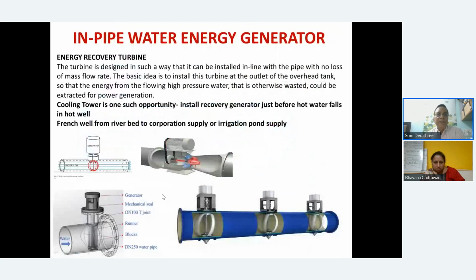Then there are in water, especially for cross country, units which are sucking water from the French wells in the river. There is maybe a 20 kilometer long pipeline of, let's say, 6 feet diameter bringing it up. For example, in a refinery or the petrochemicals here in Baroda, you will have this. When this is pumping, ultimately it has to go to a reservoir, which is just a gravity flow. So just before it goes to the gravity flow, they put the turbine so that all the pressure energy is recovered in generating power.